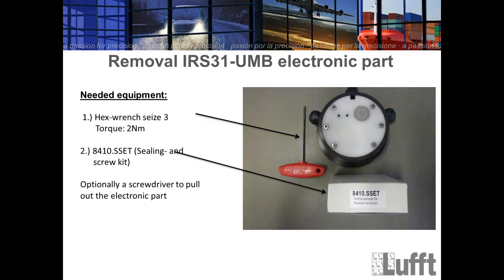Because the sealing which is used with the IRS31 needs a torque of 2 Newton meters, so that the sealing is really working the right way. So normally you cannot close the electronic part and screw the screws only manually. You need to know the power, and that's 2 Newton meters. All right? Then the second thing you need is the 8410.SSET. It's a sealing screw kit for the IRS31, which you can get from us, from Lufft. And I will show you this kit live here on the camera, and then you will see what is included. So this is the kit.